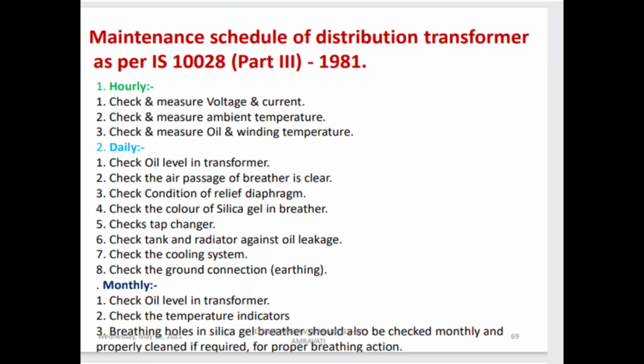So maintenance schedule of distribution transformer as per IS. So there are different types of maintenance: hourly, daily, weekly, monthly, quarterly, half yearly, and yearly. So here we see in hourly maintenance. First is check and measure voltage and current. Second is check and measure ambient temperature. Third is check and measure oil and winding temperature. In daily maintenance, check oil level in transformer. Check air passage of breather is clear. Check condition of relief diaphragm. Check the color of silica gel in breather. Check tap changer. Check tank and radiator against oil leakage. Check the cooling system. Check the ground connection earthing.